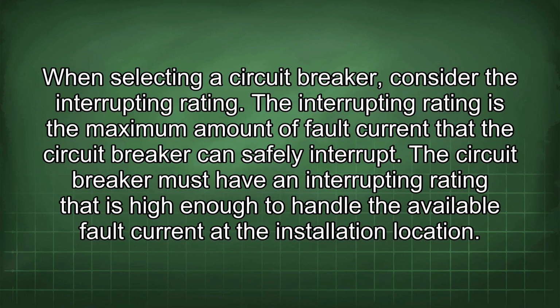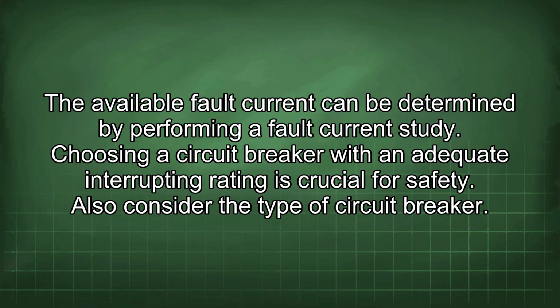When selecting a circuit breaker, consider the interrupting rating. The interrupting rating is the maximum amount of fault current that the circuit breaker can safely interrupt. The circuit breaker must have an interrupting rating that is high enough to handle the available fault current at the installation location. The available fault current can be determined by performing a fault current study. Choosing a circuit breaker with an adequate interrupting rating is crucial for safety.